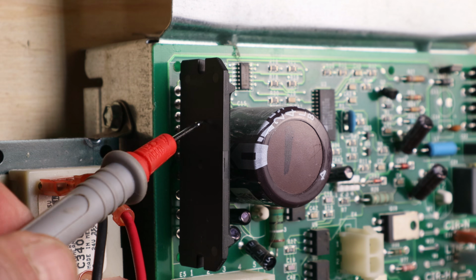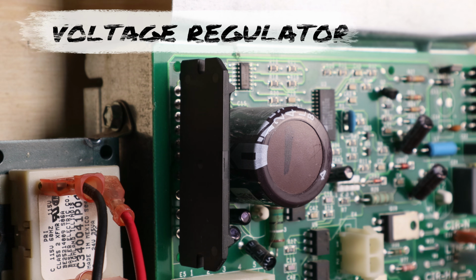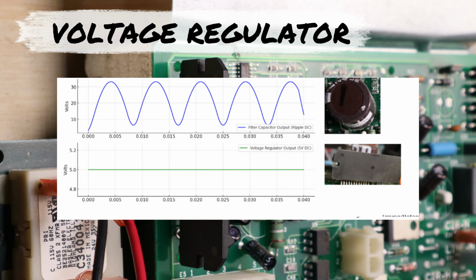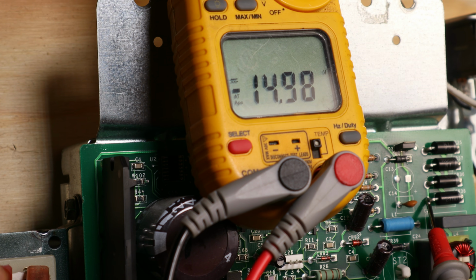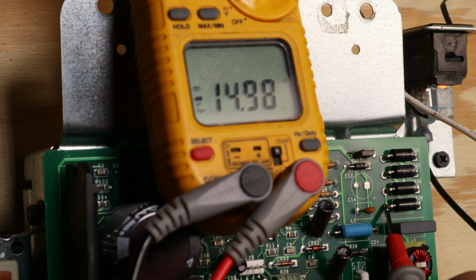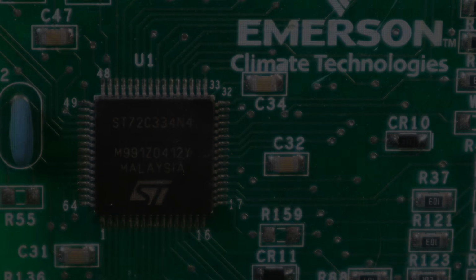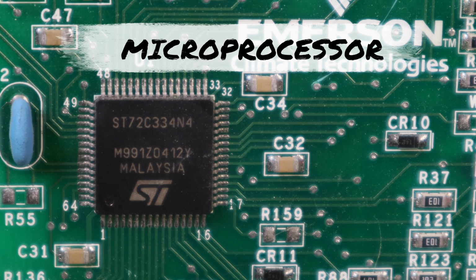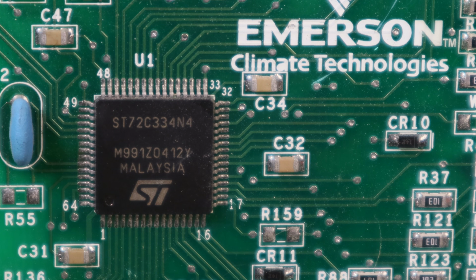Now you see this black card here, it goes there next, and that is a voltage regulator. It takes that modulating DC up and down and turns it into one single stable, steady voltage. You can see the voltage output here on this voltage regulator is a nice steady 15 volts DC. And that 15 volts DC goes straight to the microprocessor. This is the brains of the system. This is what's monitoring everything, making all the decisions, and sending the signals to the ECM variable speed motor module in order to run whatever blower profiles it deems necessary for the condition.